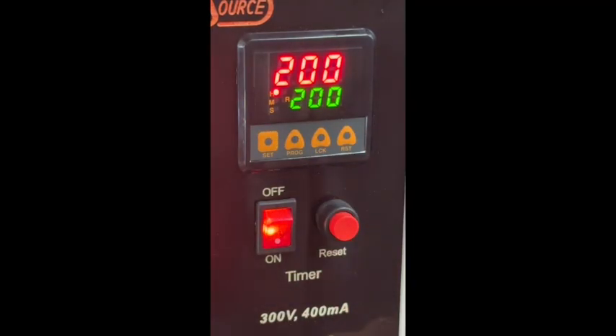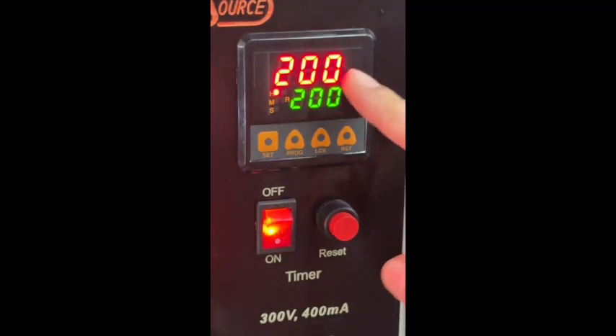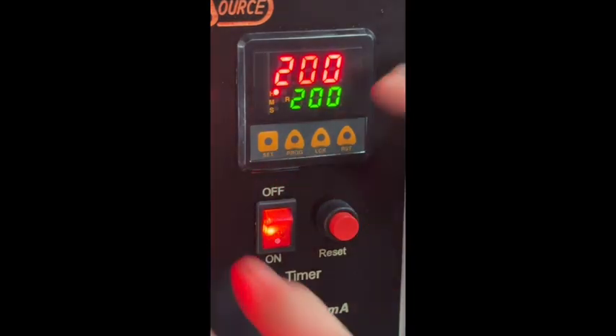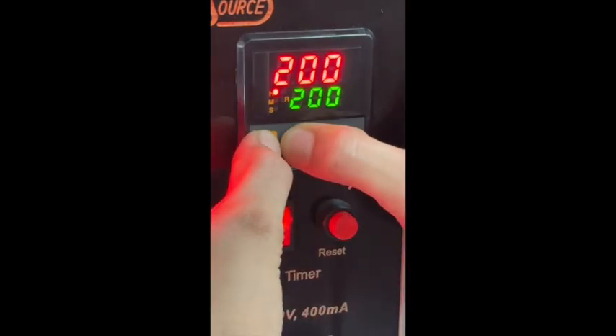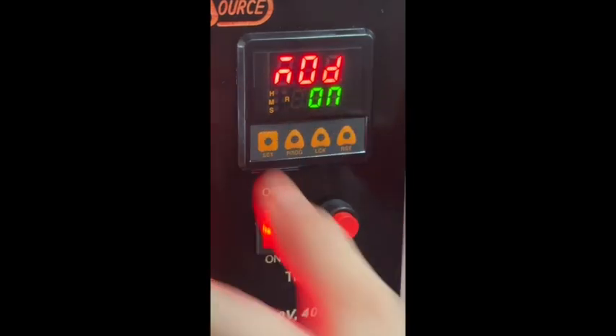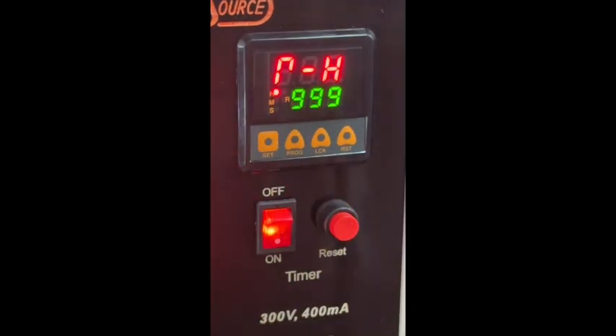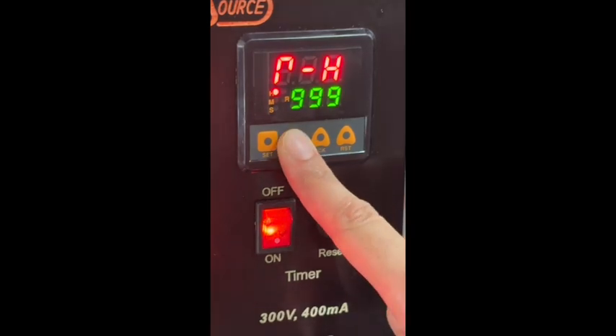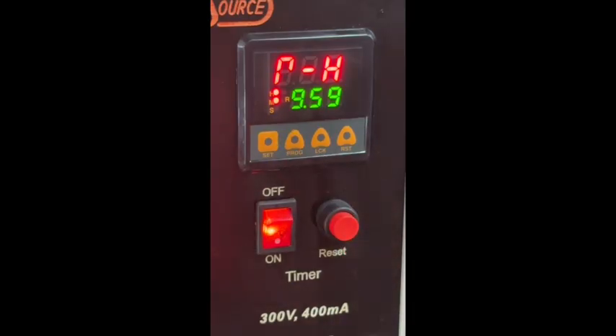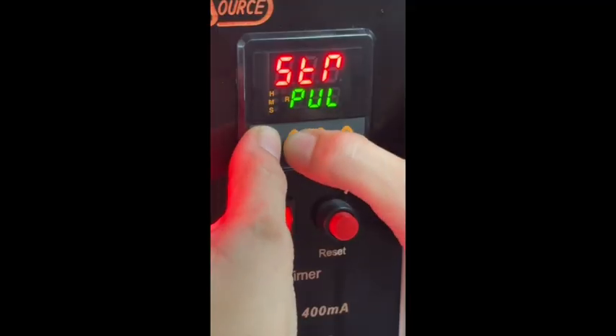We need to change the timing range again. Press the set and program buttons together for 3 seconds to enter the menu. Press set once and change the range to the desired one. For example, shown here is the hour and minute range. As you can see, the tiny red dots lighting at the corresponding positions. Press set. Exit menu by pressing set and program for 3 seconds.